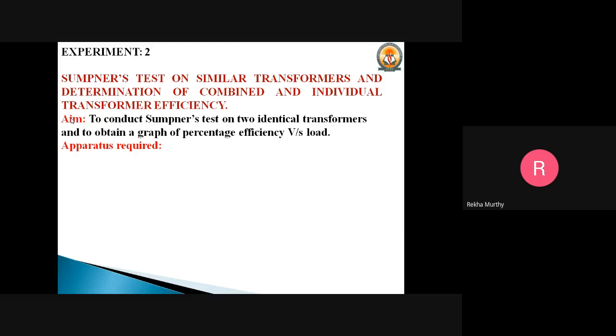For smaller rating transformers, they can be loaded by means of lamp loads or by other means. But it is very difficult to arrange suitable loads for higher ratings of a transformer for purposes of testing. And though the load is arranged in such a case, it leads to a tremendous wastage of electrical energy. Therefore, the Sumpner's experiment will help us calculate the efficiency and the regulation of the transformer.